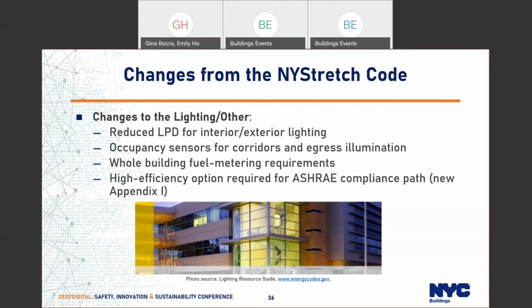There's also, so ASHRAE has had, since the last code update, a lot of fuel metering requirements and sub-metering requirements. So now whole building fuel metering requirements are required for either compliance path. So what this means is there has to be a meter for the entire building that tells you how much natural gas that entire building is using, or how much electricity that entire building is using. There's also certain sub-metering requirements that were introduced in the 2014 Energy Code that are still there, but now there's a whole building fuel metering requirement.